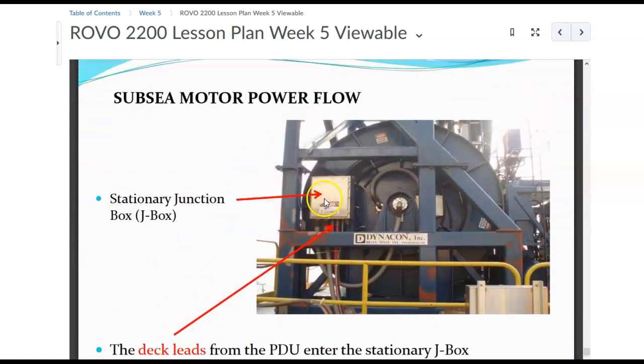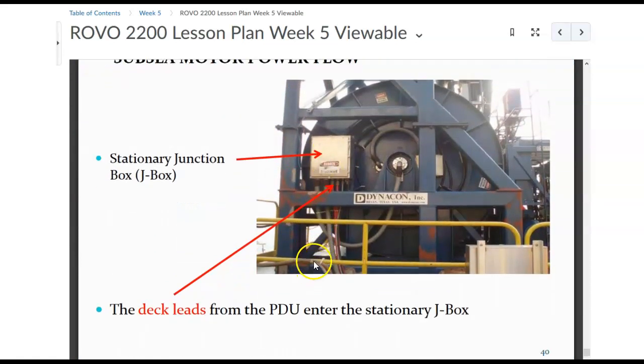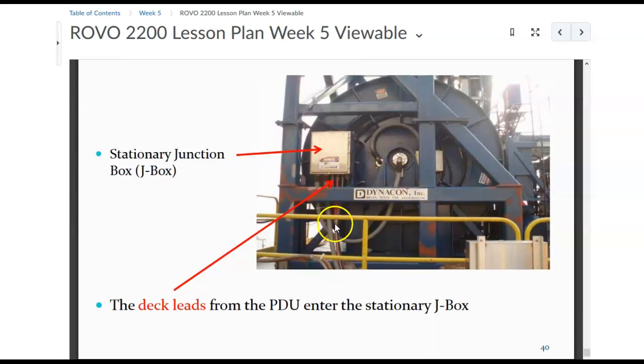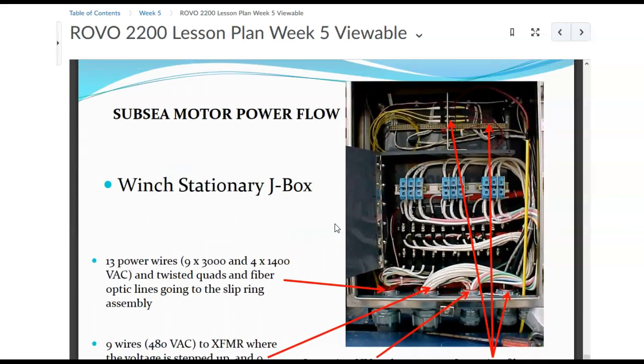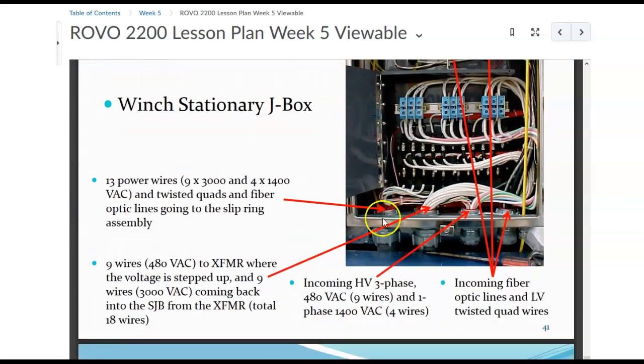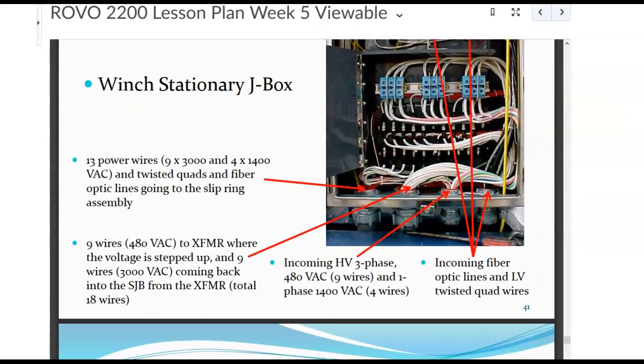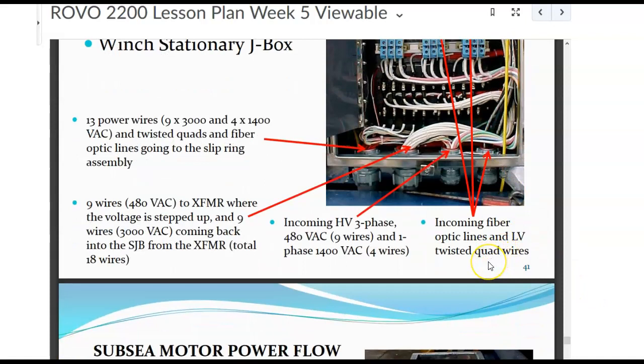Now here we go, stationary junction box. Okay, slip rings in here. And that looks like the rotating, okay, that silver one there. Deck leads from the PDU enter the stationary junction box, so it's going up inside, okay? Now this is pretty neat, winch stationary junction box. Okay, so let's just move this over. And we got the 13 power leads, 9 by the 3000, 4 by the 1400 VAC. Right, so the 3000 being 3-phase, 1400 the single phase, okay?